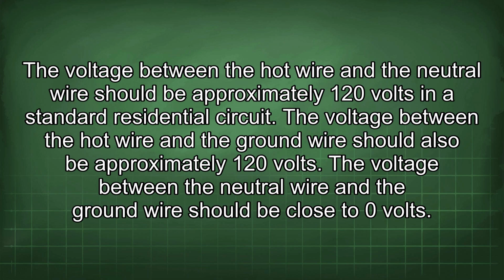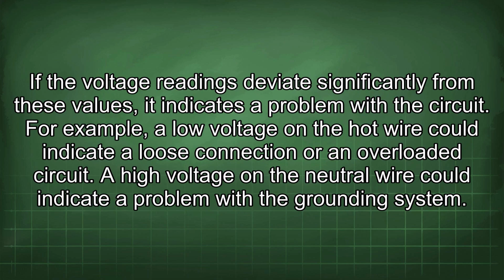The voltage between the neutral wire and the ground wire should be close to 0 volts. If the voltage readings deviate significantly from these values, it indicates a problem with the circuit. For example, a low voltage on the hot wire could indicate a loose connection or an overloaded circuit. A high voltage on the neutral wire could indicate a problem with the grounding system.